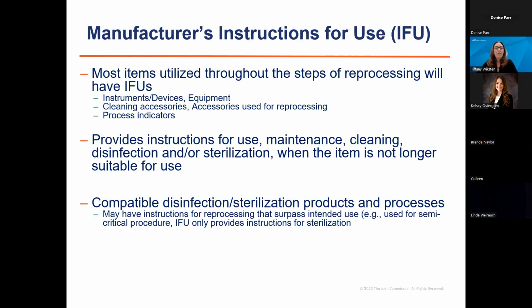So the manufacturer's instructions for use. When we talk about sterilization or even high-level disinfection, most items utilized throughout the steps of reprocessing will have instructions for use. So this includes the instruments, devices, or equipment themselves. This includes equipment like sterilizers, washer decontaminators, ultrasonic machines, cleaning accessories or accessories used for reprocessing. So pouches, sterilization wraps, sterilization containers all have instructions for use. Your process indicators, so your chemical indicators or your biologic indicators.